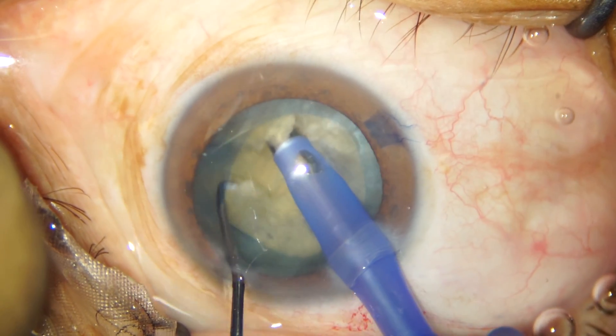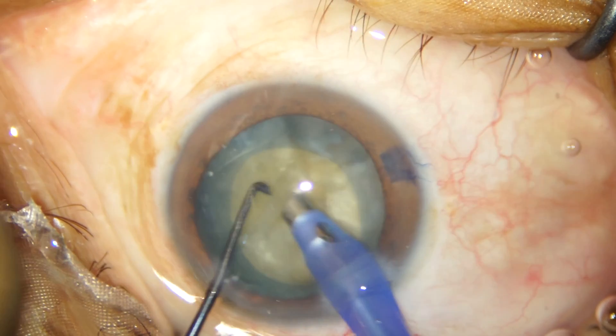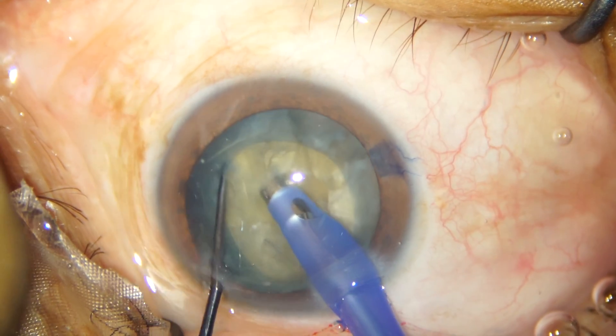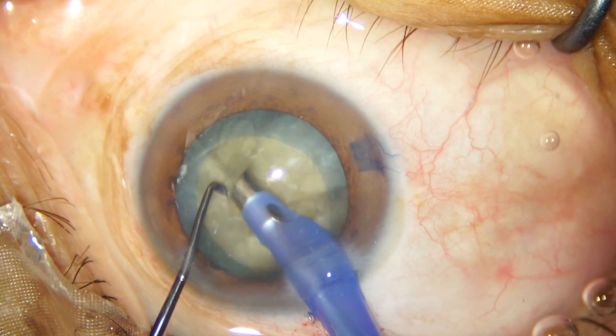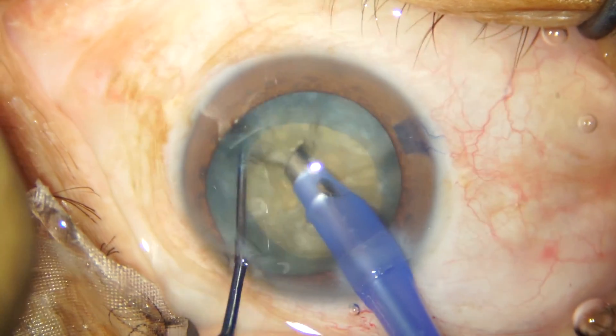My FACO settings are as such: my vacuum is 450 mmHg, the aspiration flow rate is 45 cc per minute, and I am using about 70% FACO power in a pulse power modulation of about 10 pulses per second with a 50% on time.